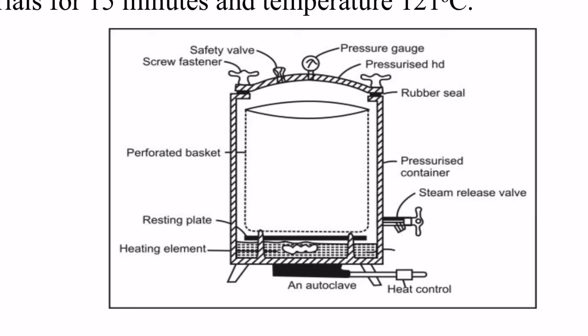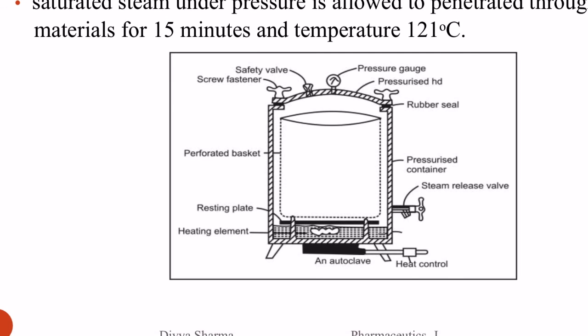The heating element heats the water, then vapors go up. If we have a perforated basket with our material and glassware inside, the steam will penetrate them. If there are bacteria or microorganisms present, steam will penetrate their cell walls and destroy them, because the steam temperature is very high. We keep the material in the perforated basket, turn it on, and when the heating element heats up, vapors rise under pressure for at least 15 minutes at 121 degrees Celsius.